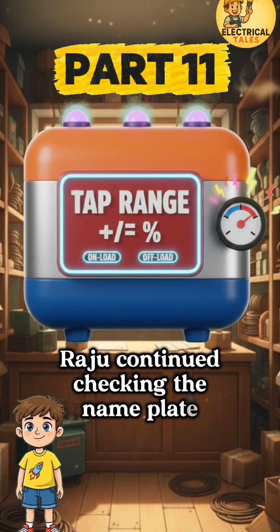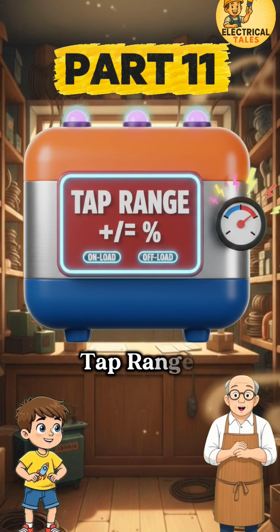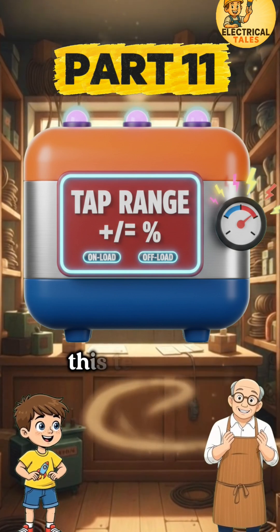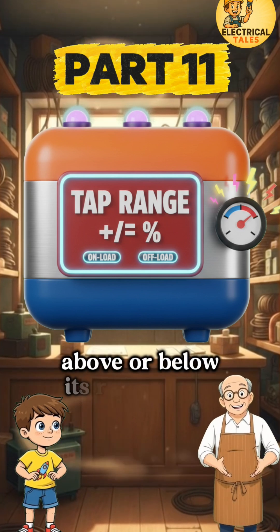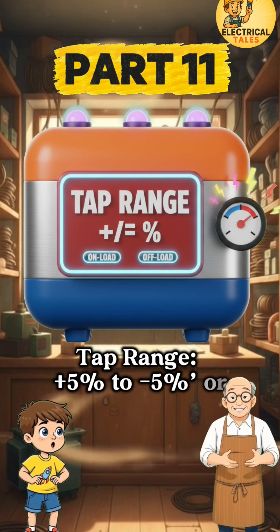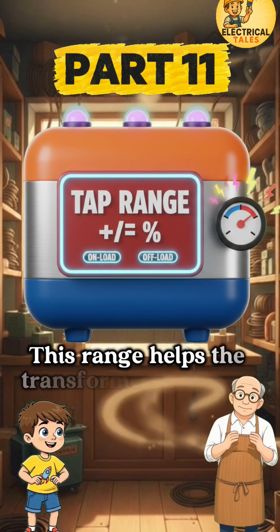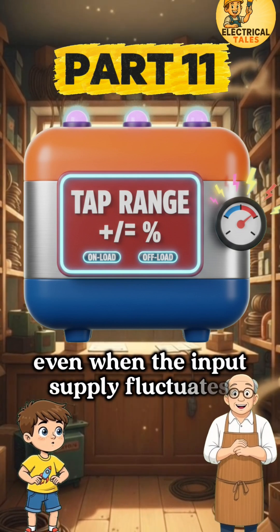Raju continued checking the nameplate when the shopkeeper pointed to the 11th one — tap range, plus or minus percent. He said, 'Raju, this tells how much the HV winding voltage can be adjusted above or below its rated value. It's written near the tap changer section as tap range: plus 5% to minus 5%, or plus or minus 2.5%.